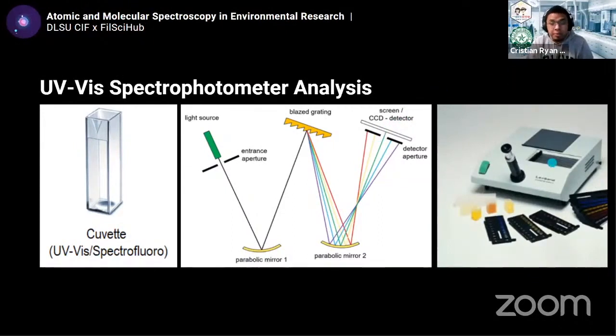Actually, there are simpler UV-Vis machines that can be used. Instead of a monochromator with a moving mirror, filters are used. For water analysis kits, most likely this is the setup because you only have limited parameters you want to analyze, so filters are sufficient. Each filter represents a wavelength. Each wavelength corresponds to an analyte - for example, phosphate, nitrate, etc. The concept of analysis involves preparing reagents with the sample.